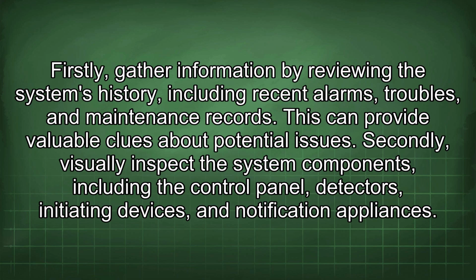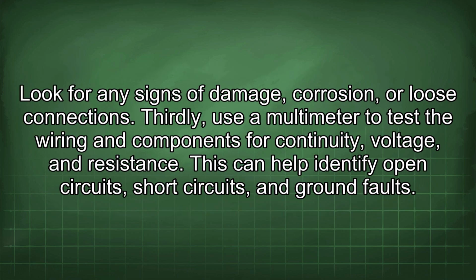Secondly, visually inspect the system components, including the control panel, detectors, initiating devices, and notification appliances. Look for any signs of damage, corrosion, or loose connections. Thirdly, use a multimeter to test the wiring and components for continuity, voltage, and resistance. This can help identify open circuits, short circuits, and ground faults.